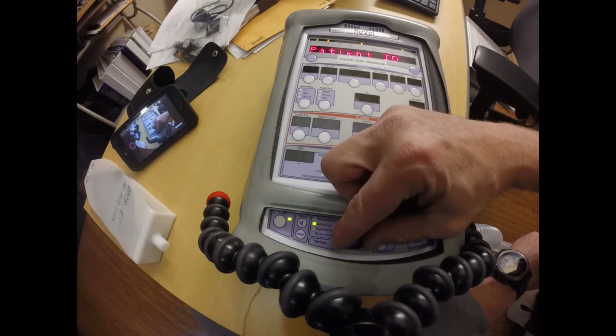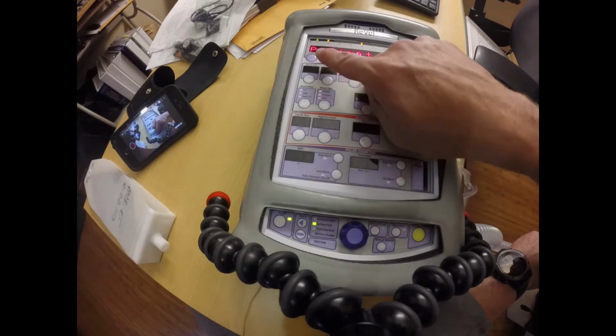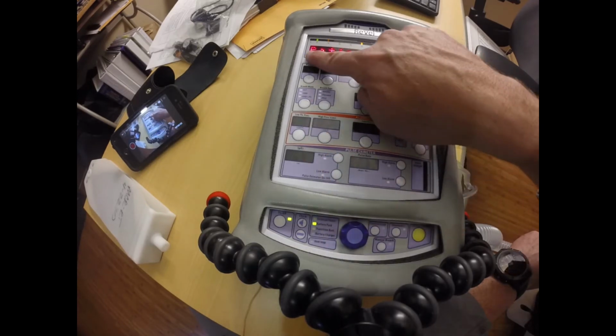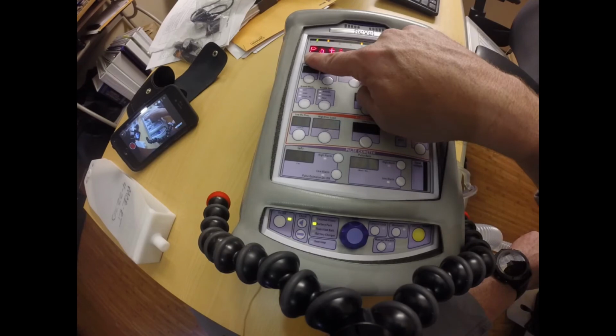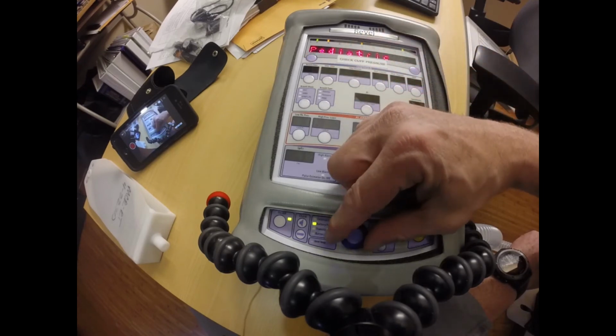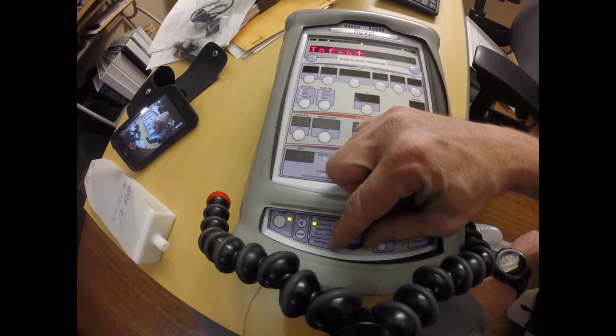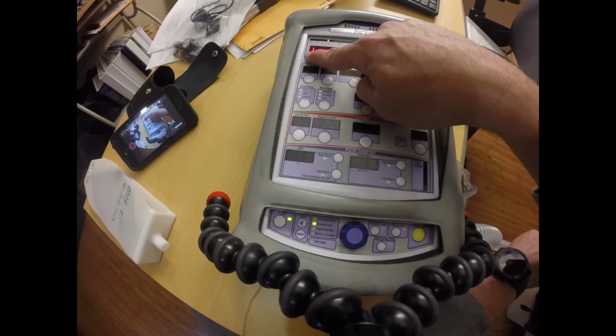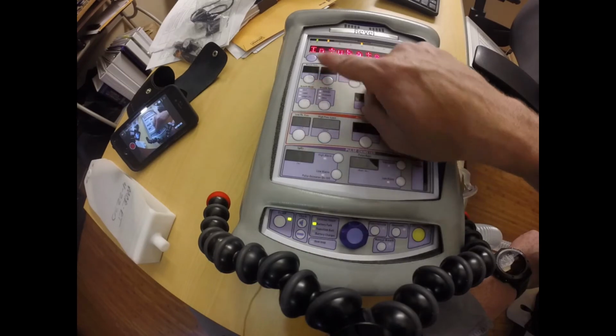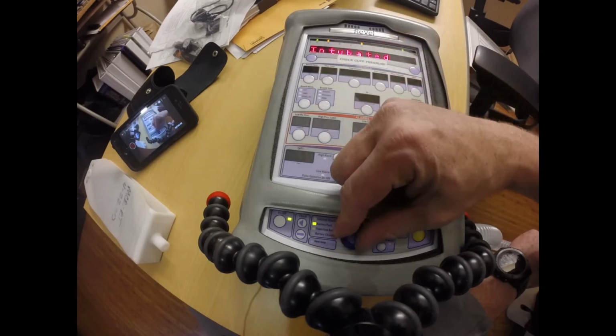Patient ID is not a parameter that we use very much. The size is. And so when I turn the ventilator on, it gives me 3 distinct sizes: adult, pediatric, and infant. Let's go ahead and start out with an adult, and I'm going to select that, and at this point it'll ask me, is the patient intubated, or do I want to use non-invasive positive pressure ventilation?